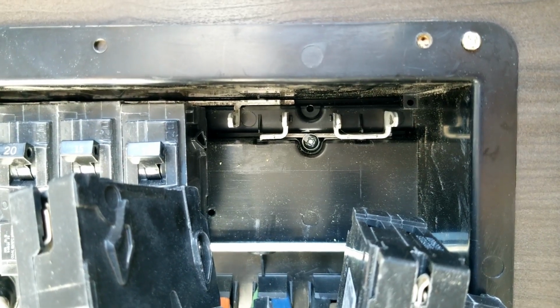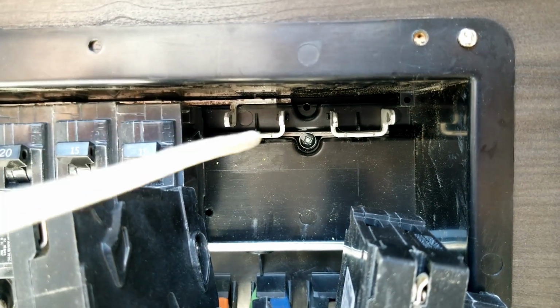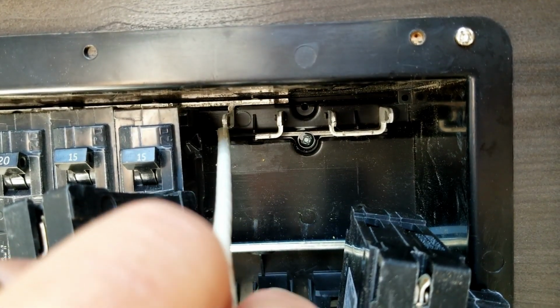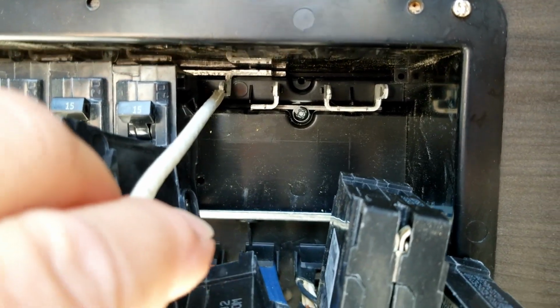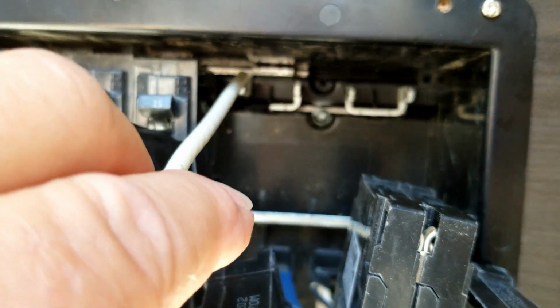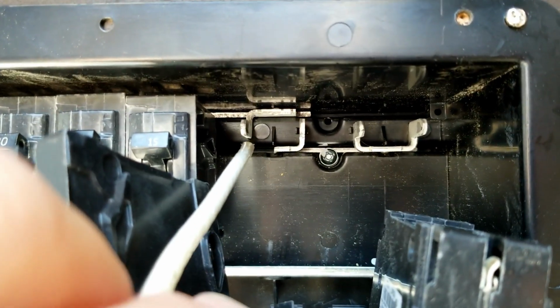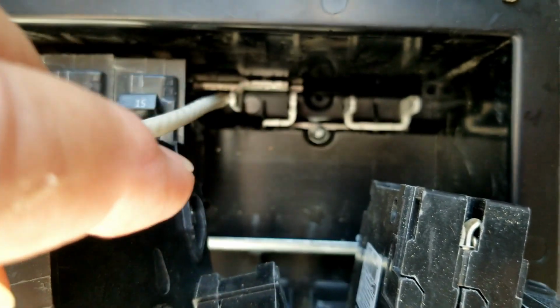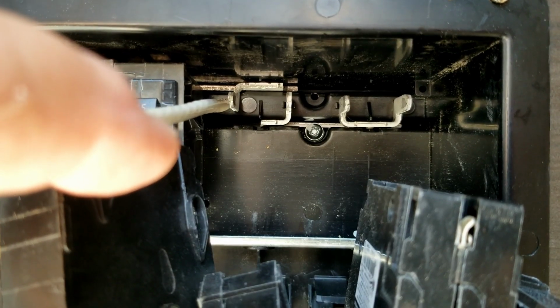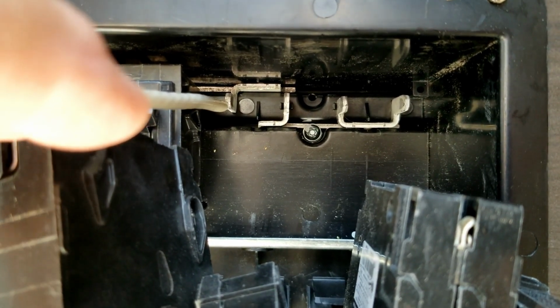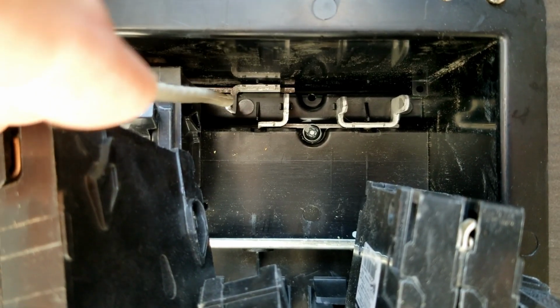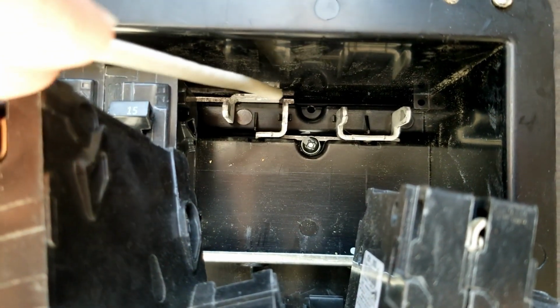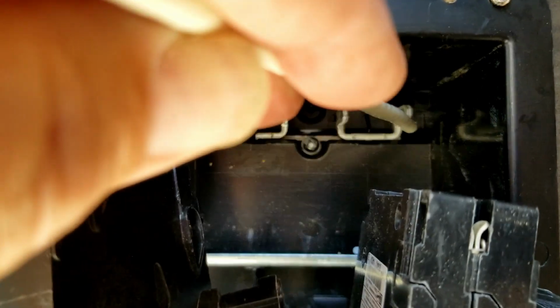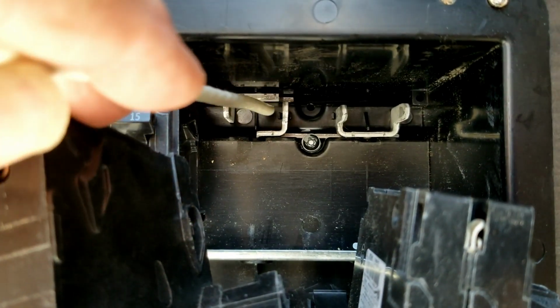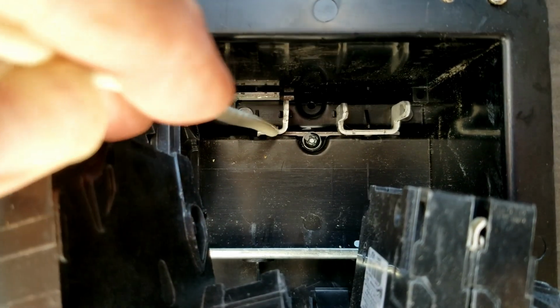Okay, so with the breakers removed, let's go back over what we had. This terminal, notice this bus bar ends right here, kind of hard to see. So this is the bus bar, and this is where that 30 amp breaker that goes out to the front on that orange Romex plugs in right here. Now if you look carefully, this bus bar is actually, there's no connection between here and here.